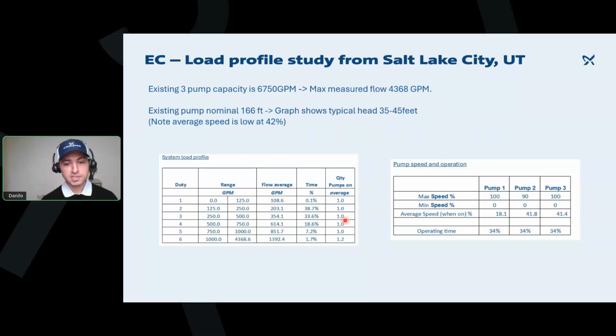So what happens in this case is that you see right there the waste of energy, right? You're now reducing the speed of those big motors to only run at this certain speed here. You see their operation, so at least one thing we know, the control installed made sure to have all the pumps running the same amount of hours, so that's well split.